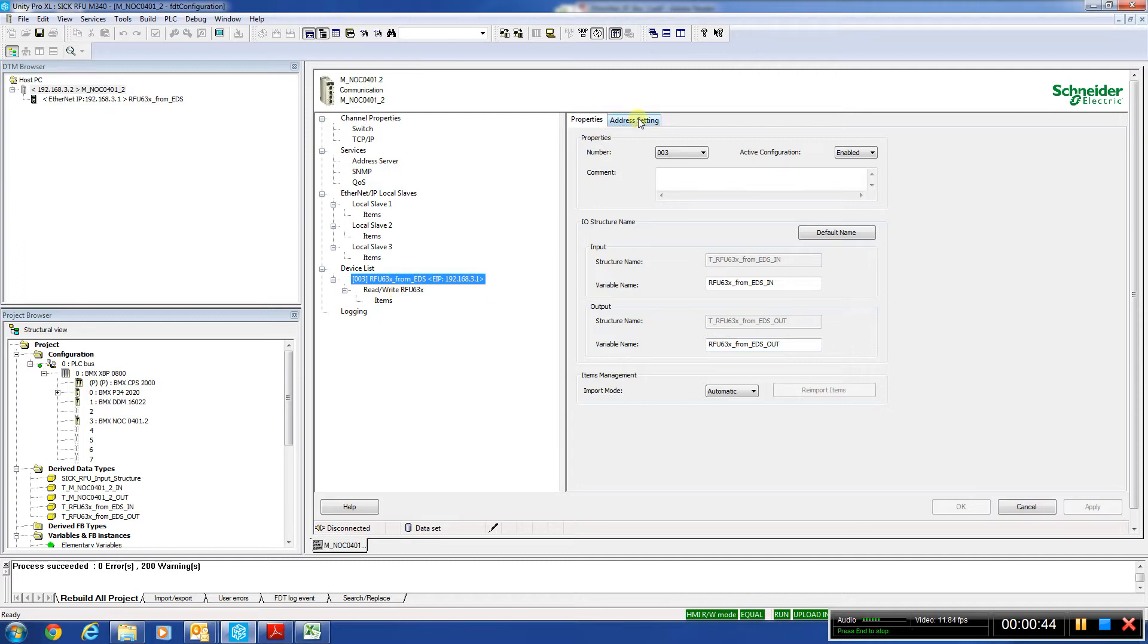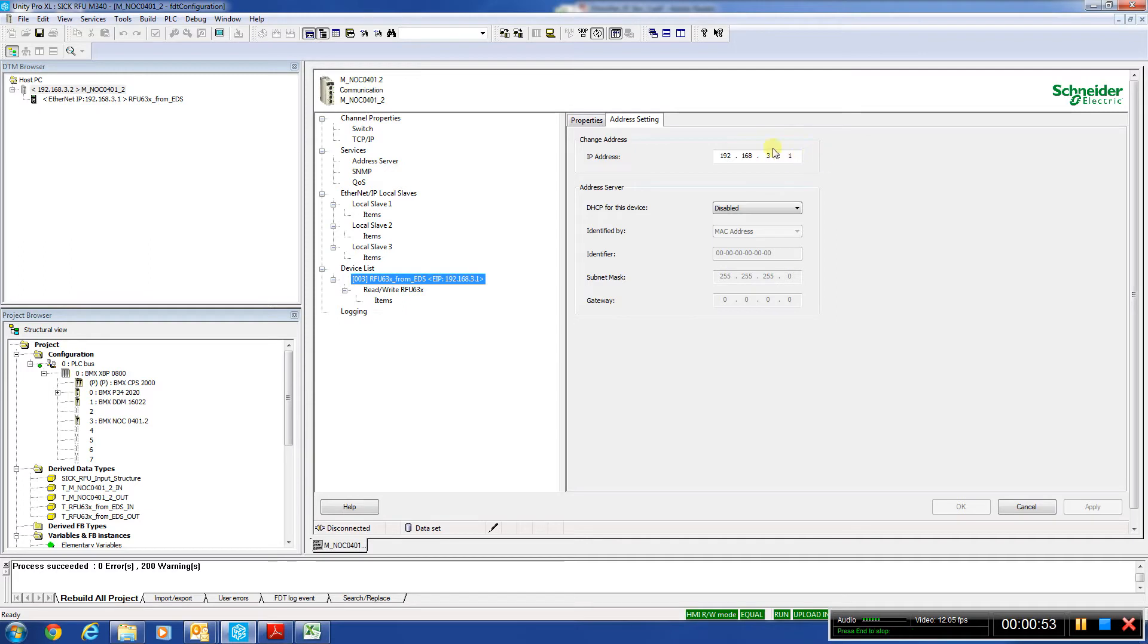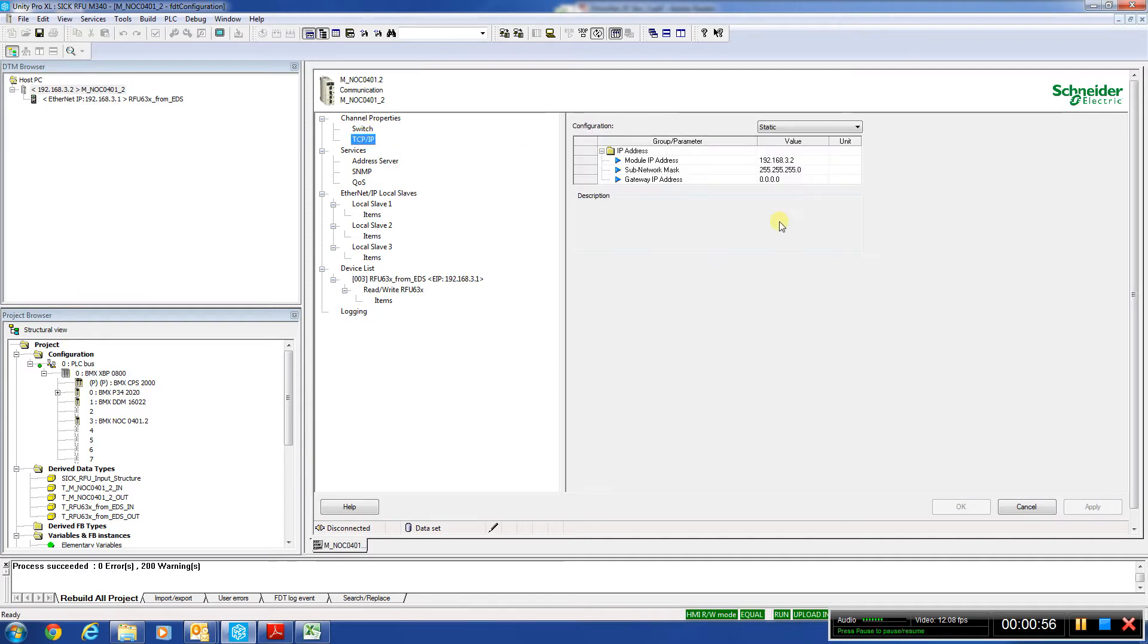If we come to the address setting, this is where we want to have the address of our RFU unit itself. Obviously, it has to be in the same subnet as the actual TCP IP up here of the card that we configured. So right there, we're in the same subnet.